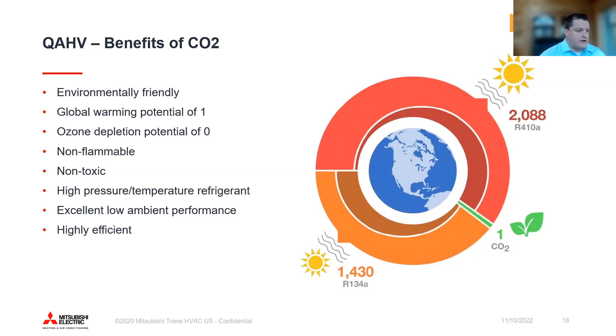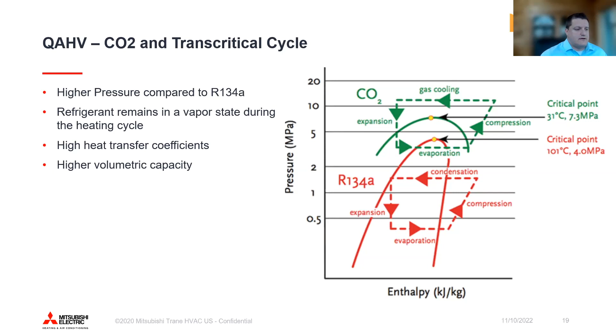So one of the key differences, like I mentioned, is that because this is CO2, this is where we gain our efficiency on the heating side at low ambient. Because of the pressure that we have in the system, and because we're above our critical point in our refrigeration diagram, we're actually just doing gas cooling on the top side of that pressure dome, right? So out of the compressor, it's going through those 6 gas coolers in parallel, and it's actually in a transcritical state that will help keep your efficiency high throughout that whole process, and that's what really likes that high delta T across the heat exchanger.